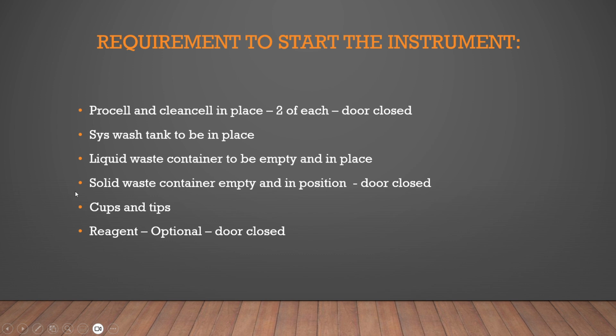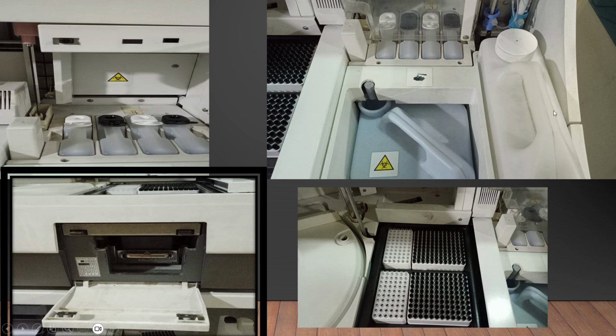Okay, so when you are switching on the instrument, you have to make sure that the pro cell clean cell is in place and the door is properly closed. The syswash tank is in. So this is the syswash tank. Around 5 liters of distilled water, and for each 1 liter, 10 ml of syswash you have to add into this, right? This is a tank which works from the downside. Down below it has a valve. So when you place it, you have to make sure that the valve is opened, and when you are lifting it also, it is a little tricky to open and close.